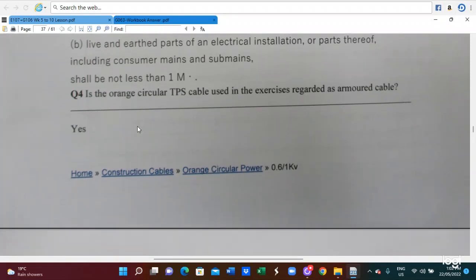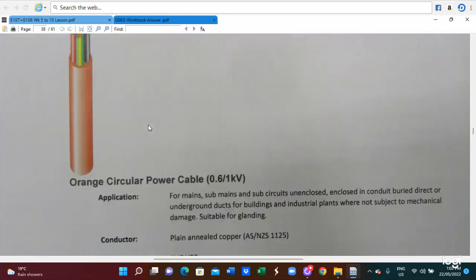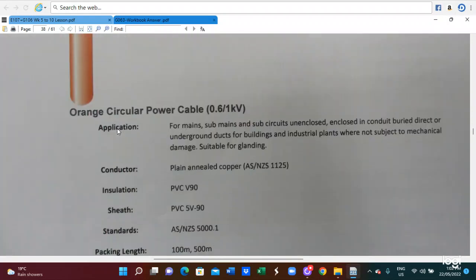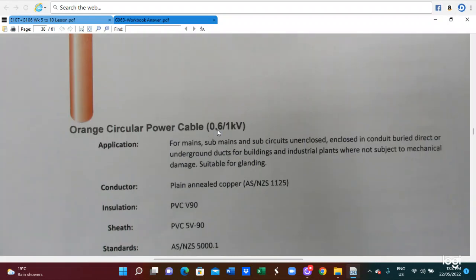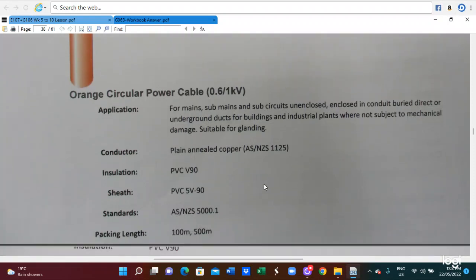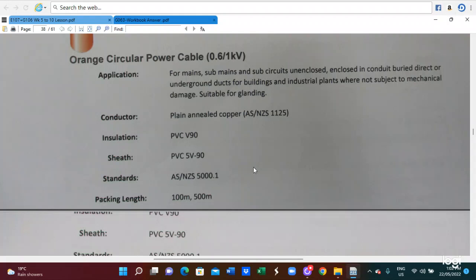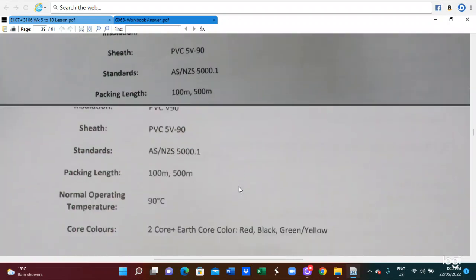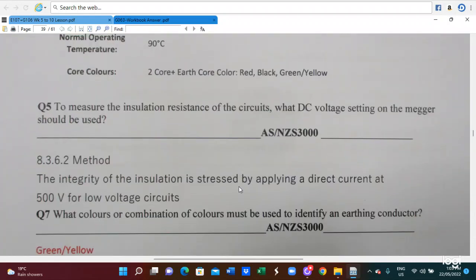Is the orange circular TPS cable used as an armored cable? Answer: yes. This is an orange circular cable, and this is for a rating of 0.6/1 kV, and this is the application. We use it for the main switchboard, sub-circuits, control, dry or underground areas. This has insulation of V-90. We have to follow AS/NZS 5000.1, with 100 meter and 500 meter lengths. So this is the kind of orange circular cable.